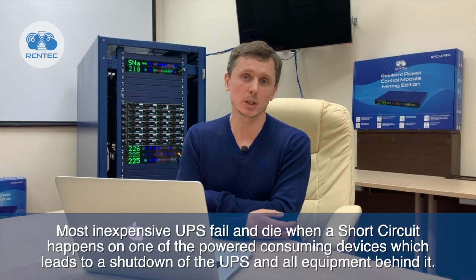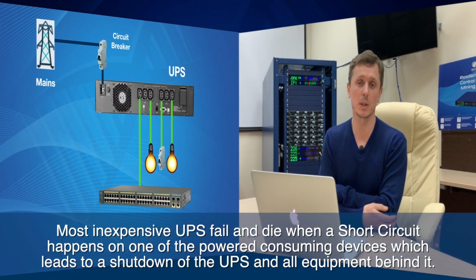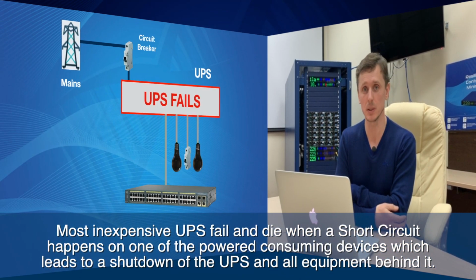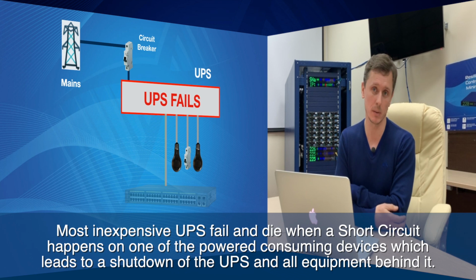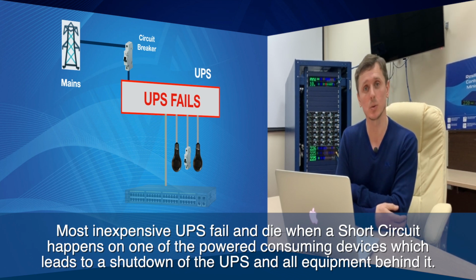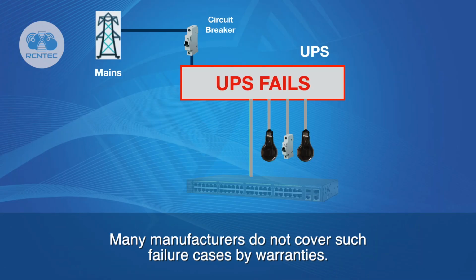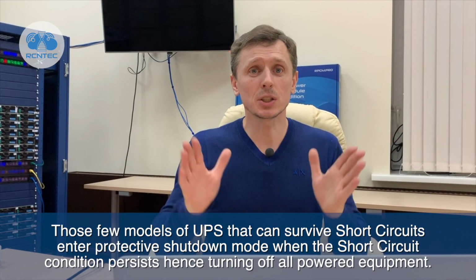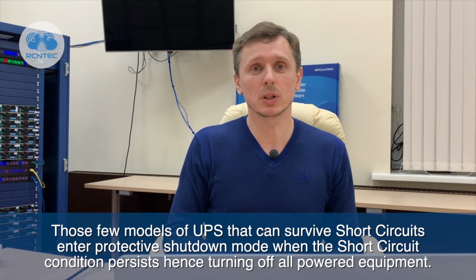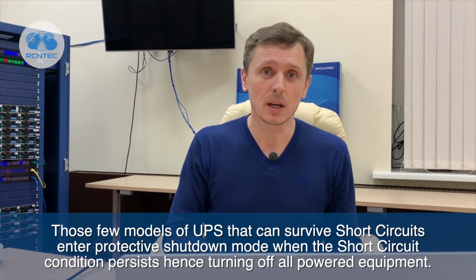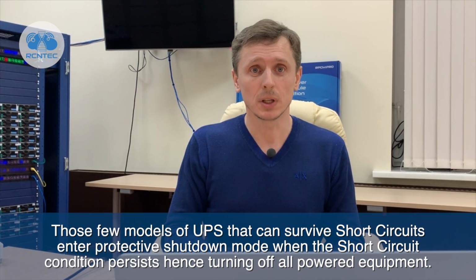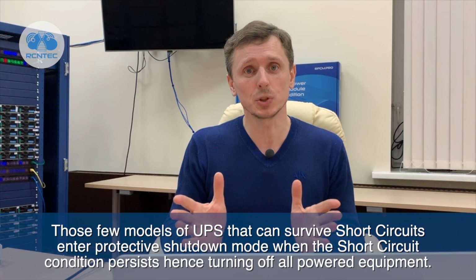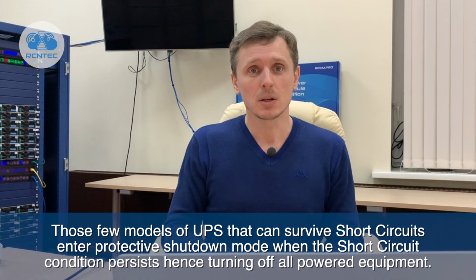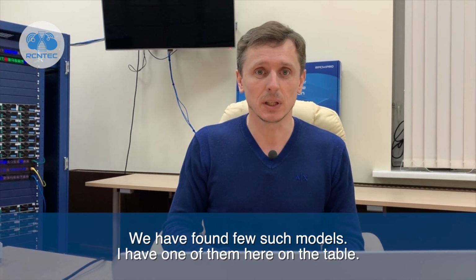Most inexpensive UPS fail and die when a short circuit happens on one of the power-consuming devices, which leads to a shutdown of the UPS and all equipment behind it. Many manufacturers do not cover such failure cases by warranties. Those few models of UPS that can survive short circuits enter protective shutdown mode when the short circuit condition persists, hence turning off all powered equipment. We have found few such models.